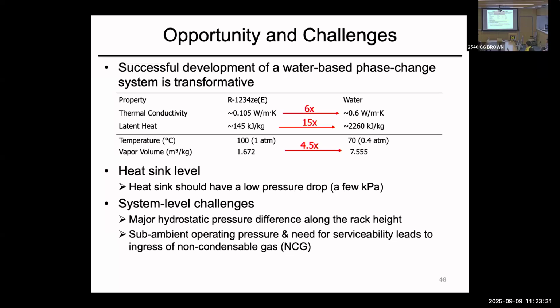Water is such a fantastic fluid. It has 6 times more thermal conductivity, which directly transfers to the heat transfer coefficient, and 15 times the latent heat. That's enormous—meaning with a little water flow rate you can cool a rack completely. But the challenge is that water boils at 100 degrees C. If you go to lower pressure, the vapor expands so much that performance can drop even below that of refrigerants.